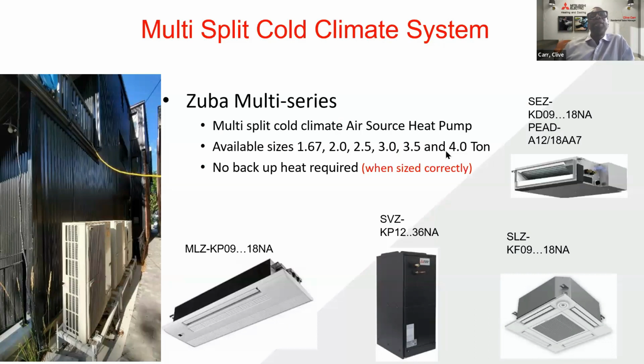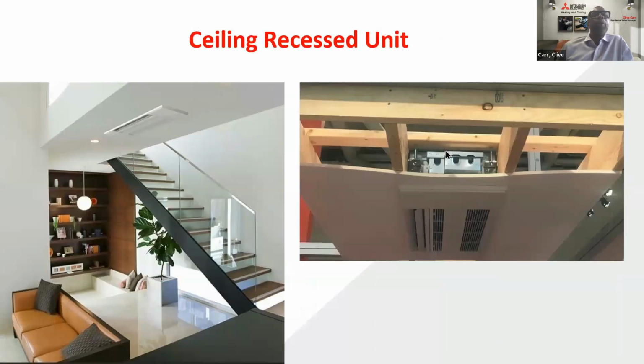Different types of indoor style units are available for our cold climate heat pump system. We've got our one-way cassette, which is more aesthetically pleasing than, let's say, a low wall mounted or a high wall mounted product. One of the cute things about this product is that it fits between 16-inch on center joists, and the cavity is less than a foot. It's approximately 8 inches in height, so it will fit right within the ceiling cavity based on today's standard for residential home development.